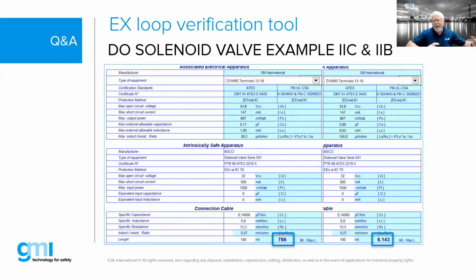What I've commonly seen is you might have a control drawing with maybe 20 different transmitters, but using the same exact transmitter and the same exact barrier, with a maximum cable length of say 1,000 meters or 500 meters, whatever that calculation length is. Then on your control drawing or DSD, you'll have tag numbers 1 through 10 and so on. So instead of creating 20 drawings, you create one drawing with 20 tags. But yes, it is a requirement to do a DSD.